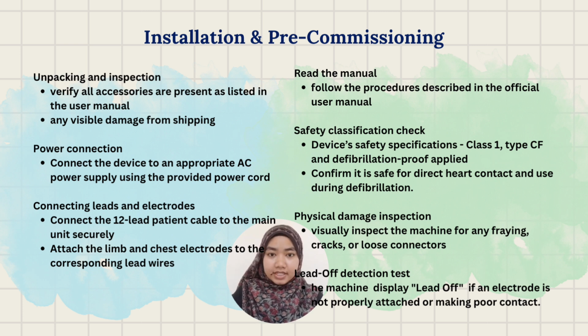For pre-commissioning, first read the manual and follow the procedure described in the official user manual. Second, safety classification check. The device safety specification is class 1, type CF, and defibrillation-proof applied. Confirm it is safe for direct heart contact and use during defibrillation. Third is physical damage inspection. We need to visually inspect the machine for any fraying, cracks, or loose connectors. Last is the lead-off detection test. The machine displays lead off if an electrode is not properly attached or is making poor contact.